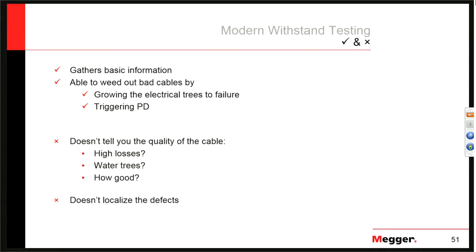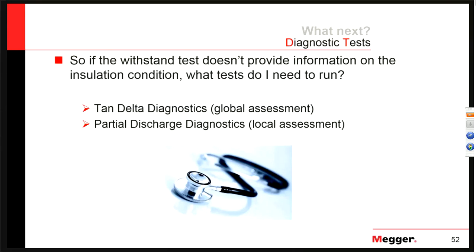In summary, basic VLF withstand testing gathers basic information about cables — it's able to weed out bad cables and weak spots by growing electrical trees to failure. What it cannot tell you is how well the cable is — whether it just barely passed or passed very easily — or if there are significant water trees or high losses. It also doesn't localize defects; the only way to find the weak spots is to cause the cable to fail and then use cable fault equipment. That's where diagnostic tests come in — tan delta for global assessment of overall insulation condition, and partial discharge for local issues like splices and terminations.